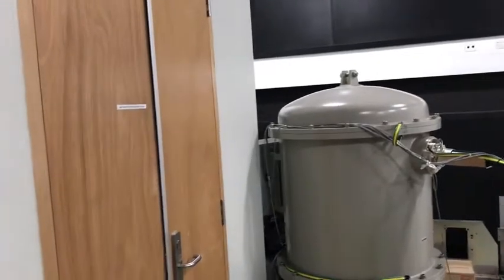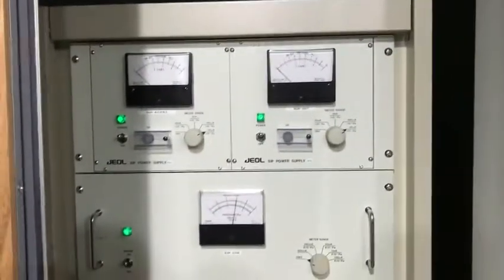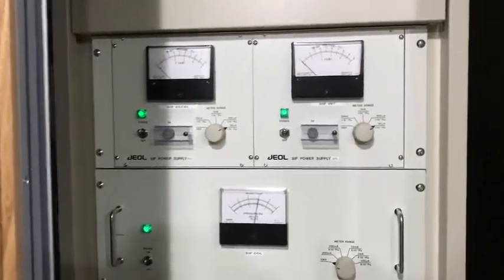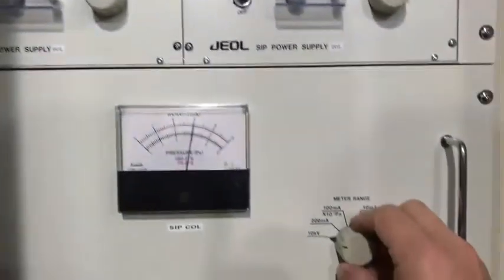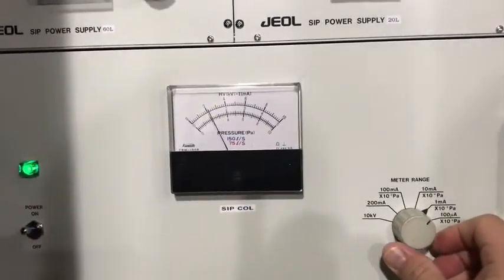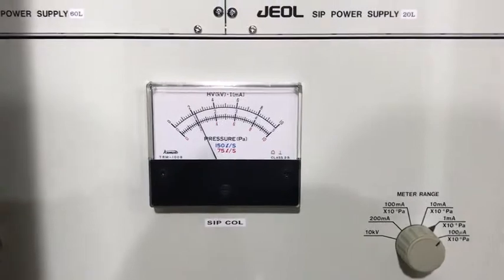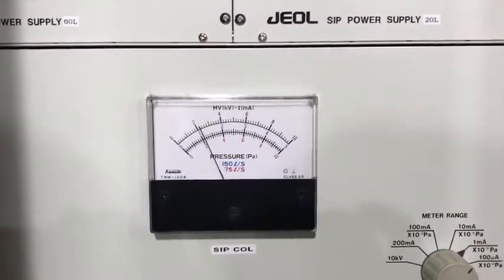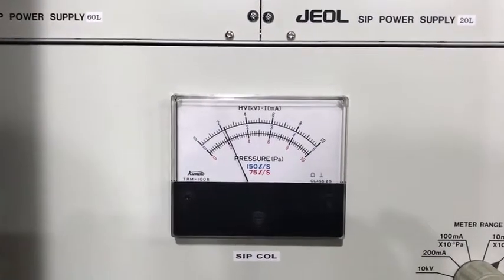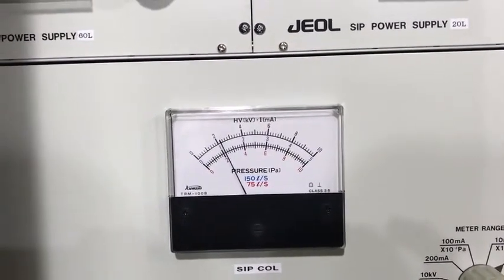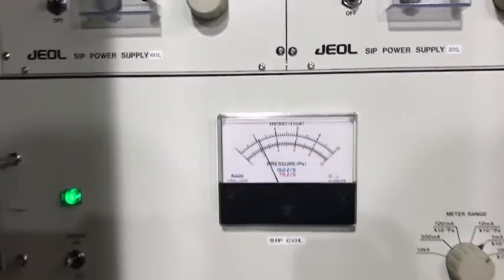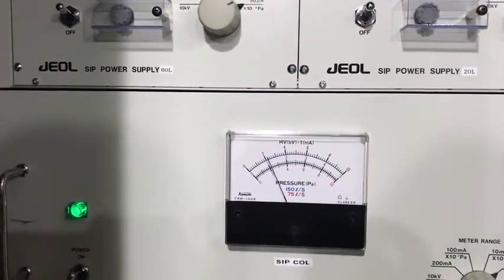There is the sulfur hexafluoride pressure in the high tension tank, and that looks fine. That's on the red mark. Now I'm sorry for the shakiness. Going to the vacuum monitors, the gauges. I'm just going to switch this gauge to 10 to the -5. It's funny doing this on camera. And that gauge there shows that we're at a nice pressure, 1.1 by 10 to the -5 pascals. So that's about 10 to the -11. Sorry, 10 to the -10 atmospheres.